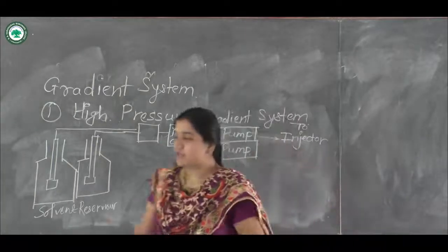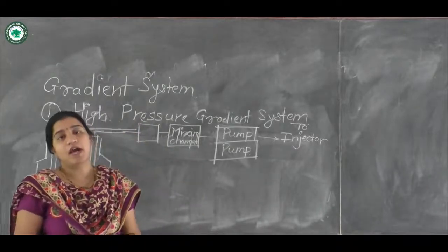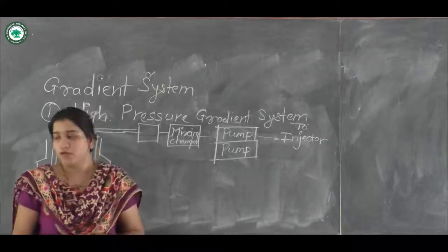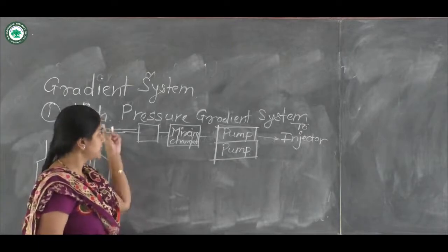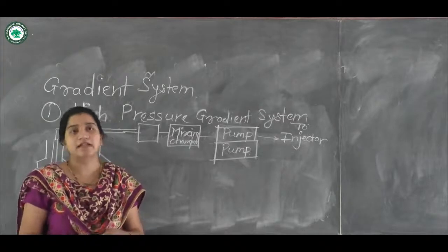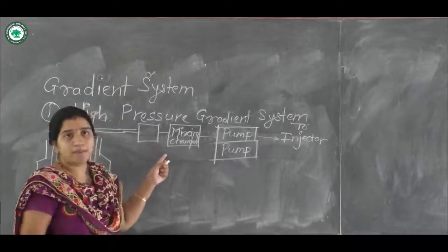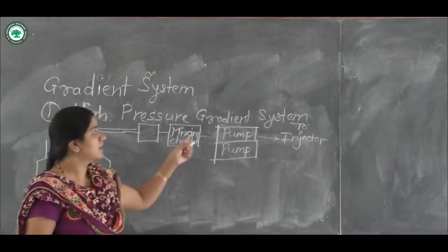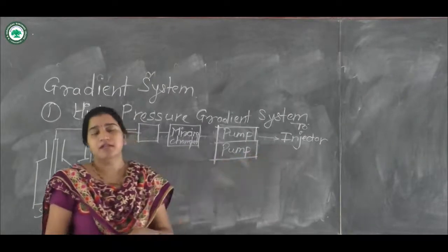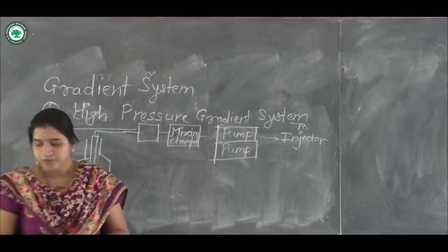Since you are applying more pressure, you are using two or more pumps. Here again the solvent is kept inside the solvent reservoir. After that, proper mixing of solvent and sample takes place. Then after passing through the pump, your sample is ready for injection in the high pressure gradient system.